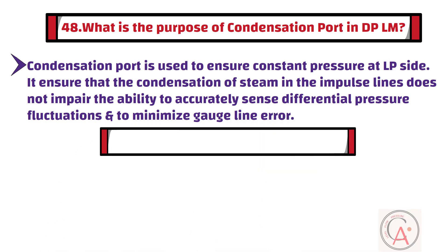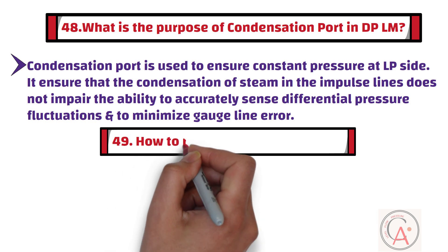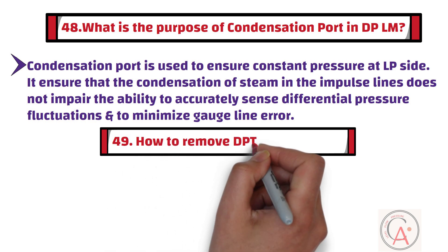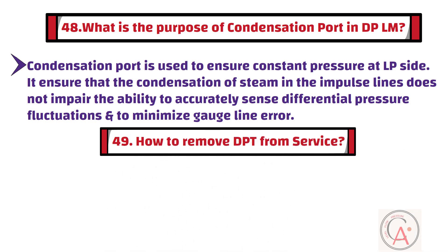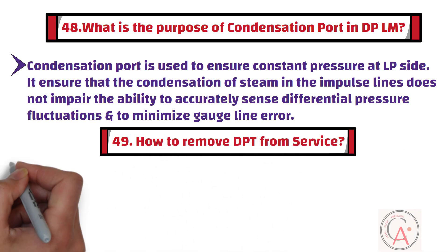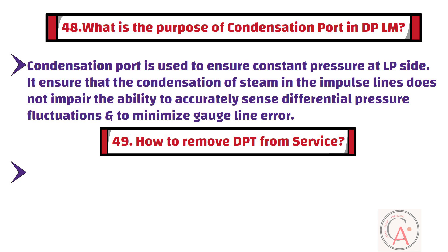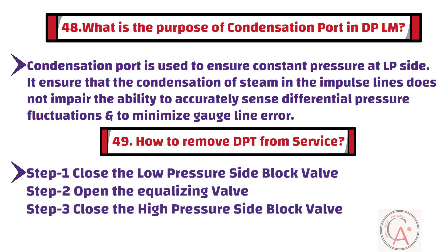Question 49: How to remove DPT from service? To remove DPT from service, first close the low pressure side block valve. Secondly, open the equalizing valve. Finally, close the high pressure side block valve.